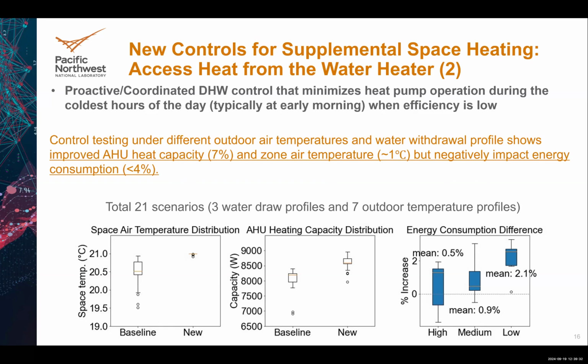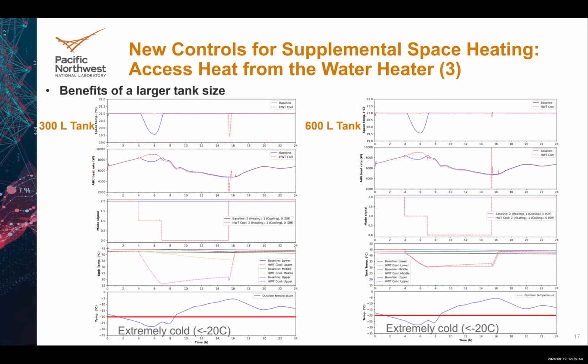You want to increase your space air temperature during the cold period, but there is a balance, because later you still need to charge back the tank. So that's why you consume more energy than the baseline, but the total consumption is less than 4% compared to the baseline. Here we want to further investigate the benefit of a larger tank size, because you want to use the heat stored in the tank, right? Ideally, if you have a larger tank, the tank can provide enough heat for the discharging process. So here we compare the default tank, that's the 300 liter, and the double size tank.